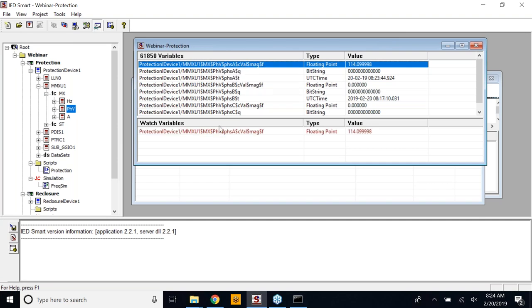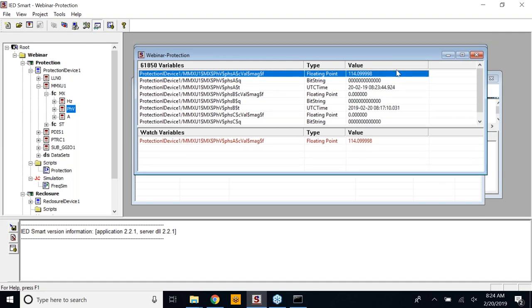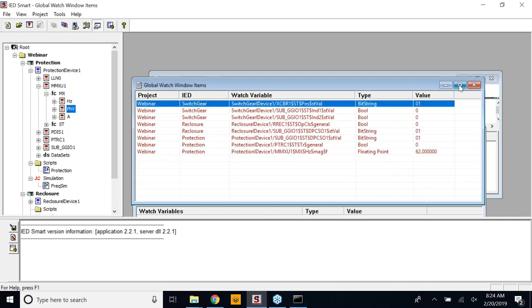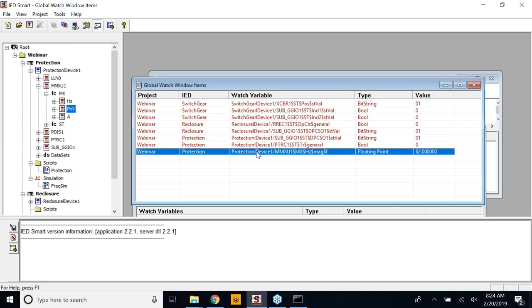There is an option to add data points to the local watch window, which is something you see when you select a specific IED, so it doesn't have a global scope. We also have a global watch window where we can monitor multiple data points from all three IEDs. The protection device's frequency data point is listed here. Right now the value is 62 — it is slightly an odd value, kept intentionally to generate some abnormal conditions. We have a conditional simulation based on this abnormal value.